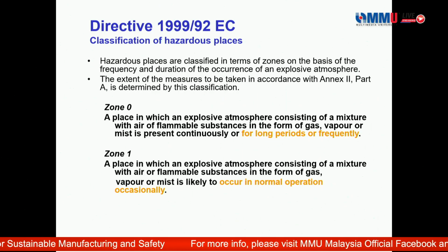For gas exposure we have zone 0, zone 1, or zone 2. Zone 0 means the gas, mist, or vapor is present indefinitely for a long period of time, making it the most dangerous zone. Zone 1 is where the substance is present, but only during normal periods, not for a long time. Zone 2 is similar, but the vapor is present for only a very short period of time.